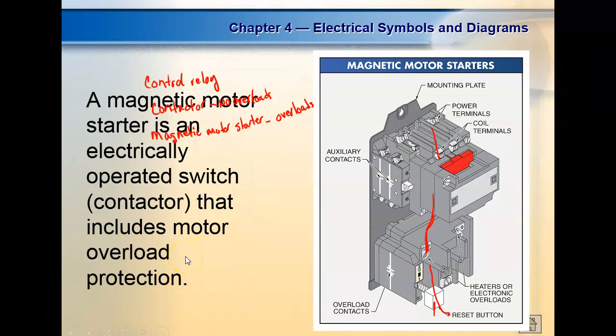Contactors don't have overloads. It don't mean they don't run motors. It's just that the motors usually have the overloads built into them, right? You understand? We see some single phase motors that actually have resettable overloads on them. They'll have a little red button on the back, and you can actually reset the overload, which are neat. They don't do that. So that is a magnetic motor starter.